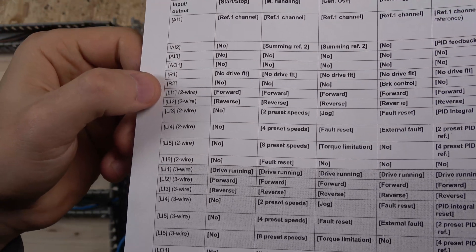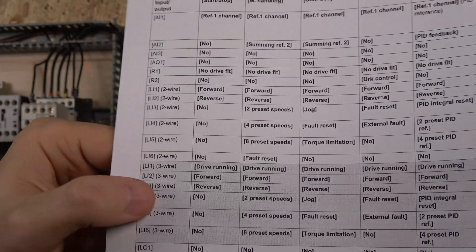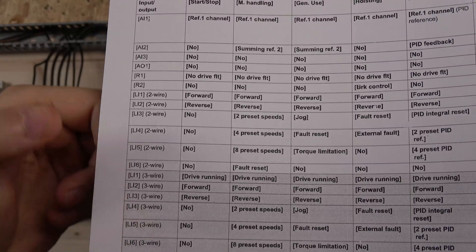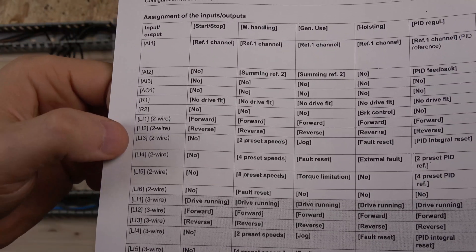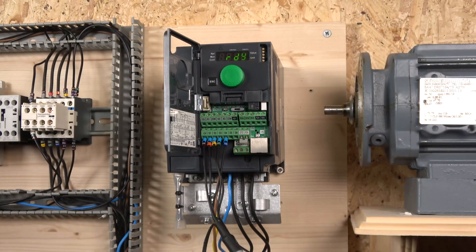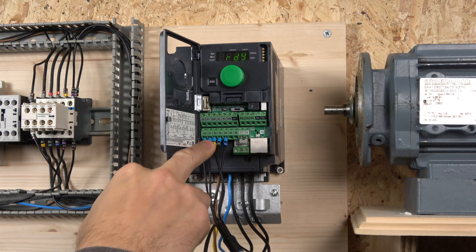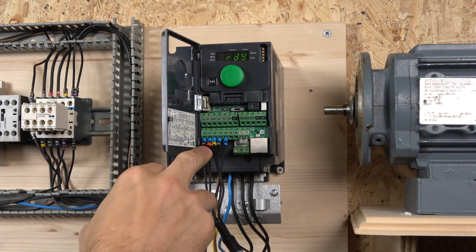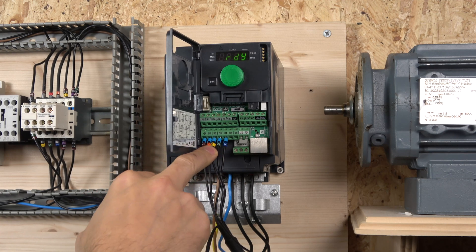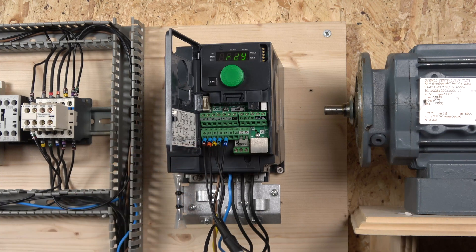As you can see, LI1 and LI2 are used — don't use those yet. I haven't tried three-wire control but you can definitely try it; this setup is going to be two-wire control. LI3, LI4, LI5, and LI6 are unassigned. I chose that macro to be able to assign the inputs freely. I've wired forward run, reverse run, speed up, and speed down to LI3 and LI4.